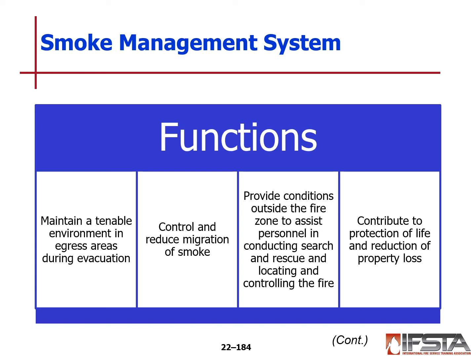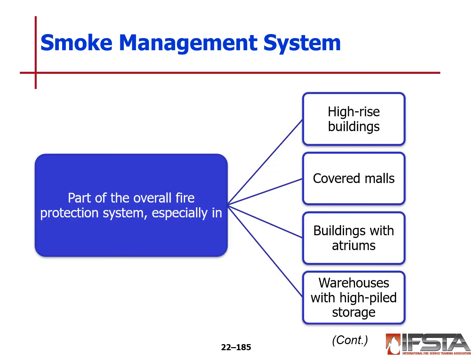The function of your smoke management system, again, is to maintain a tenable environment in egress areas during evacuation. You find these systems a lot of times in stairwells. They'll pressurize the stairwell to keep the smoke out. If smoke does enter, then it is exhausted out. They function as a control and to reduce migration of the smoke. They provide conditions outside the fire zone to assist personnel in conducting search and rescue operations and locating and controlling the fire. And they may contribute to protection of life and the reduction of the loss of property.